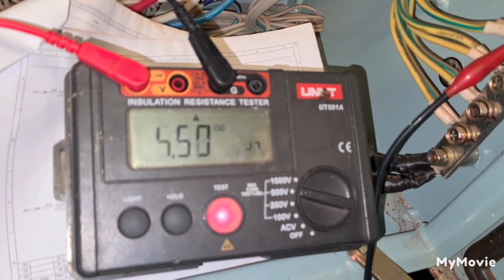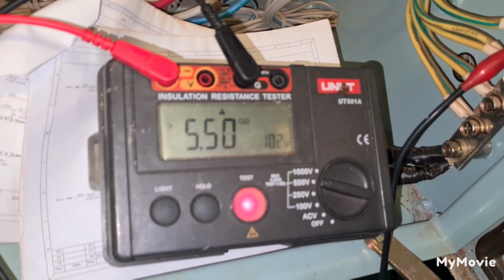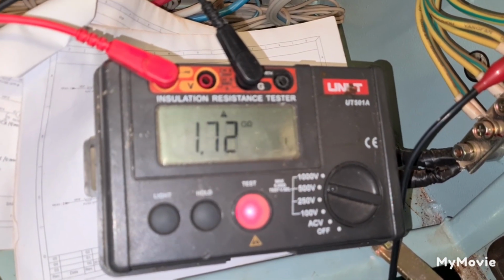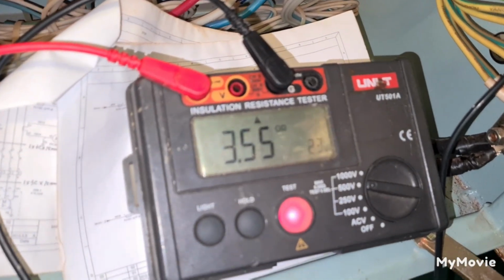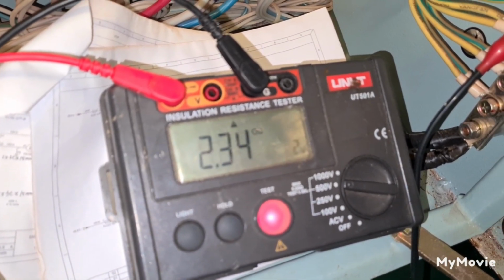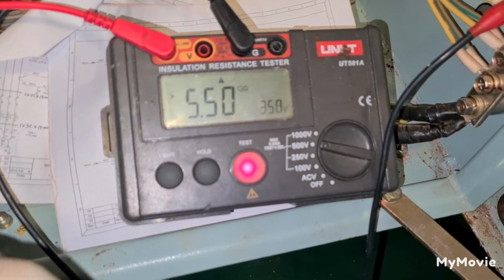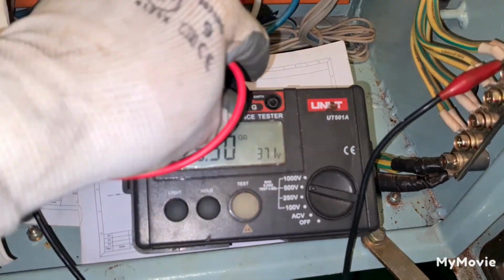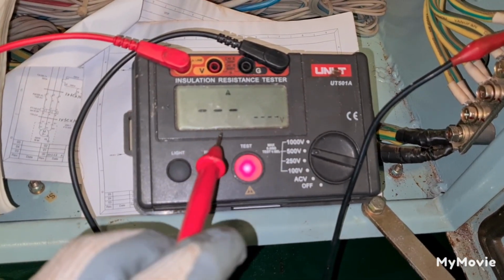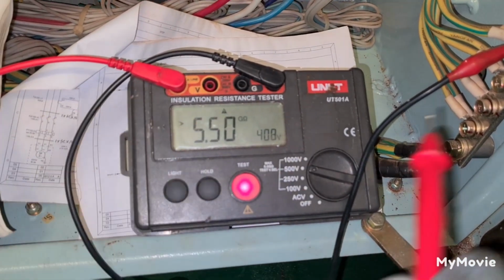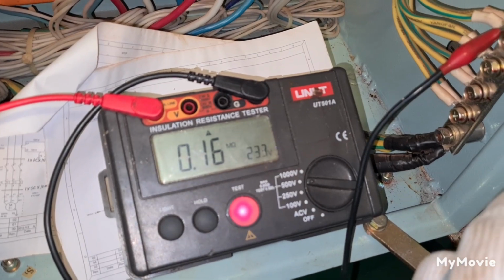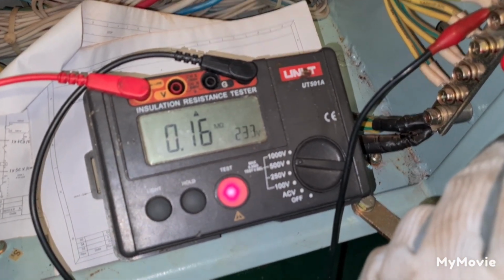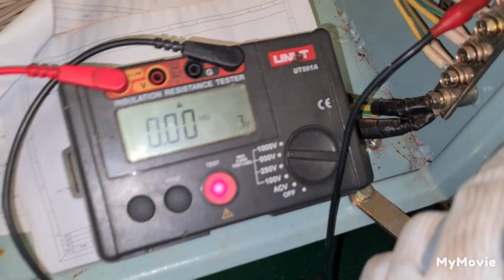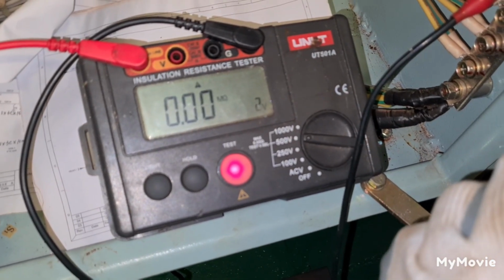You see, if it is in good contact, you see, there is a buzzing sound, 1.84 gigaohms. See, but if I try to put this in earth, we can have a value of earth. Okay, this is earth, this is B. See, 0.16 megaohms. So this is an indication of not good.